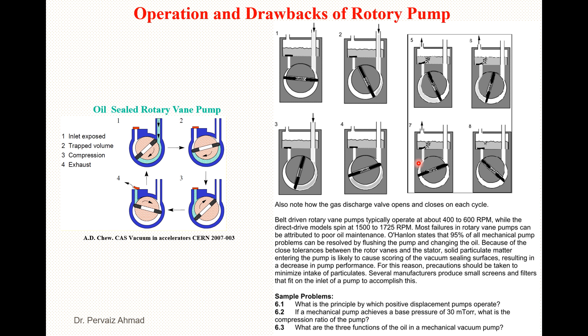It is stated that 95% of all mechanical pump problems can be resolved by flushing the pump and changing the oil. Because of the close tolerances between the rotor, vanes, and the chamber, solid particles entering the pump are likely to cause scoring of the vacuum sealing surfaces, resulting in decreased pumping performance. Precautions should be taken to minimize particle intake; several manufacturers produce small screens and filters that fit on the pump inlet to accomplish this.